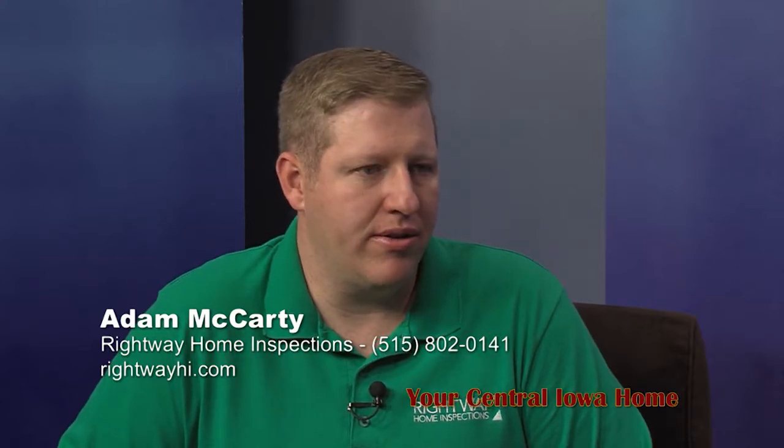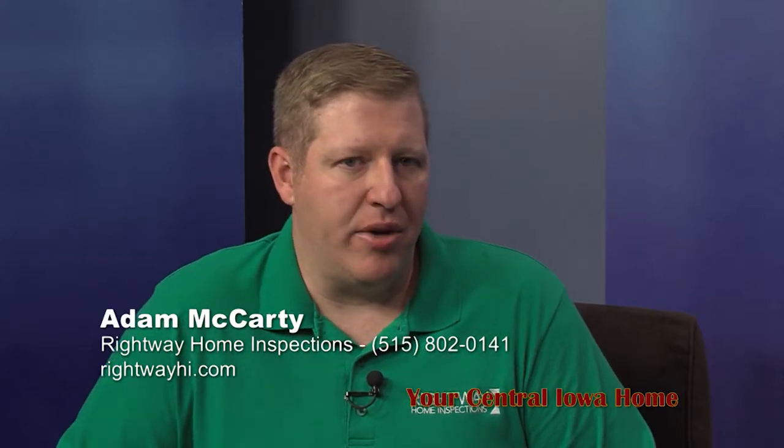Sure. Do you check on the heating and cooling systems? Yeah, I always look at the heating and cooling systems. I take all the front panels off, all the maintenance panels that you would normally take off as yourself, and make sure I watch them burn. I'm looking for a nice blue flame on natural gas flames, and just look at everything, make sure everything looks good, no rust. You know, looking at age also.